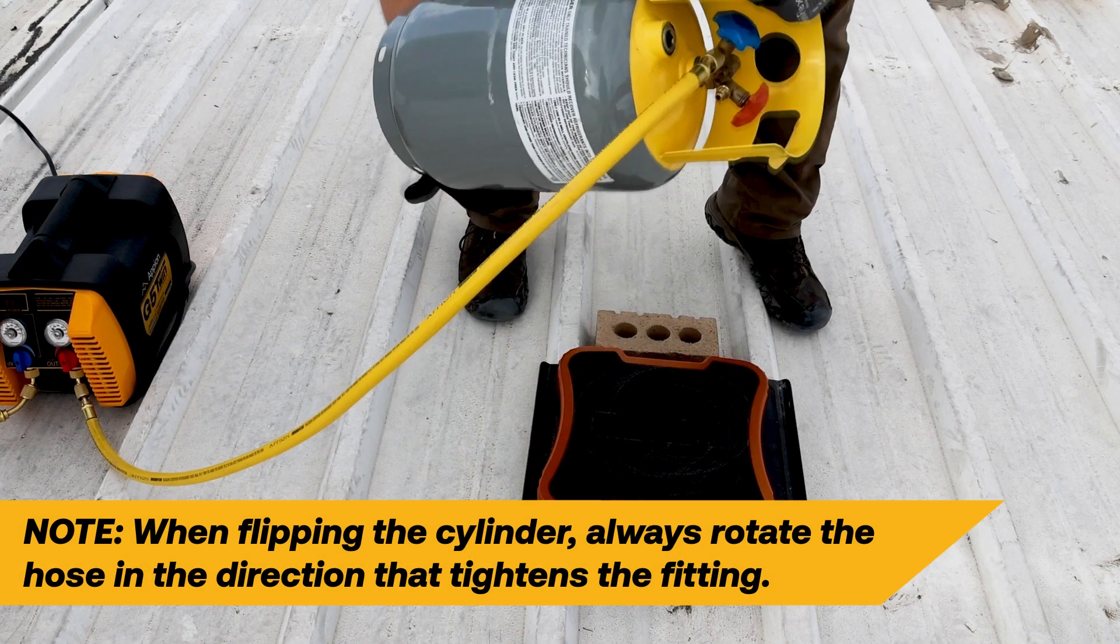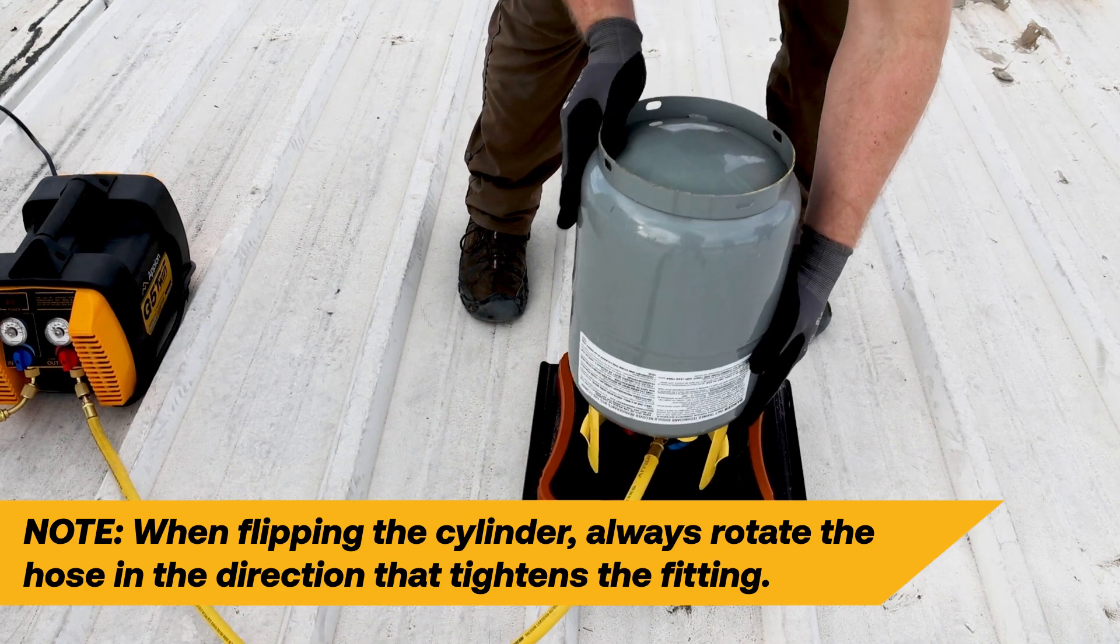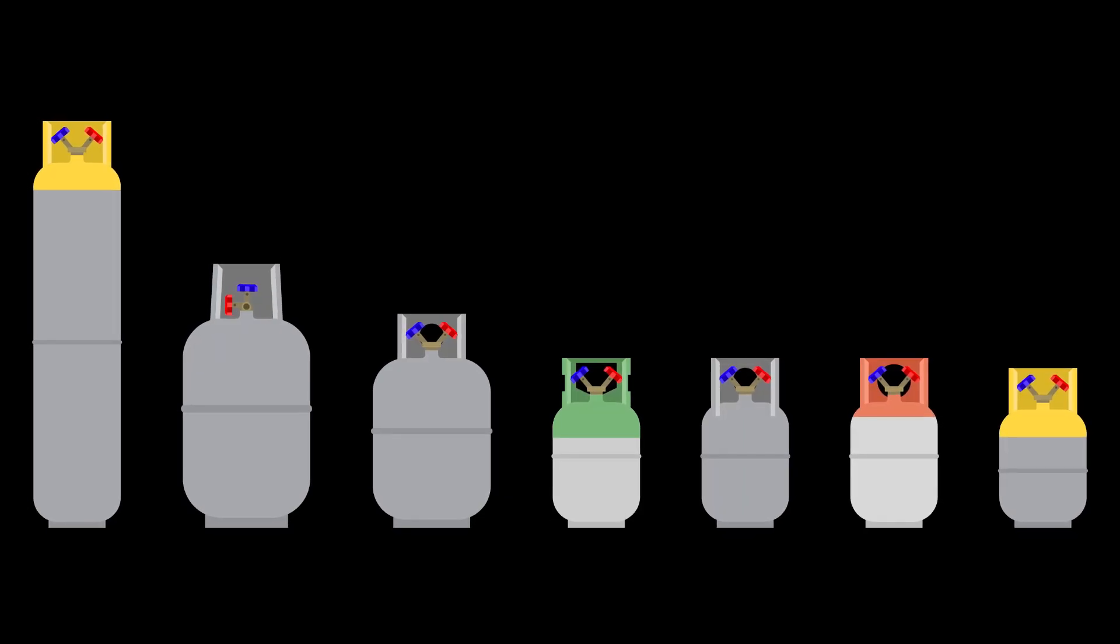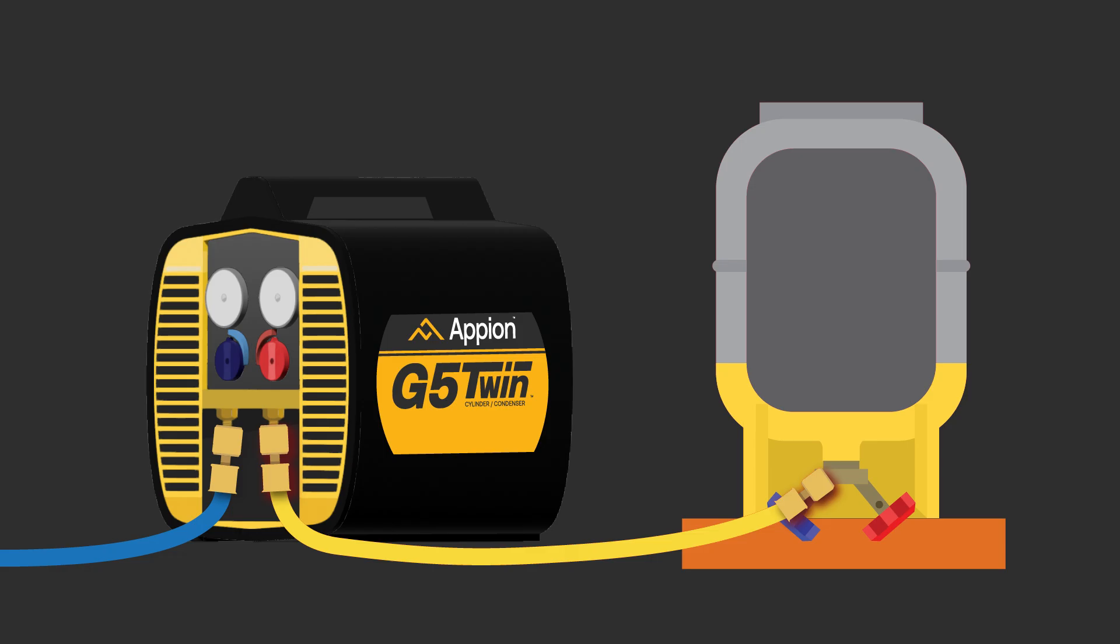One of the easiest add-on techniques is flipping the recovery cylinder. While this technique can only sometimes be used due to limitations with recovery cylinder design and weight, it is often a great technique to utilize when applicable. Flipping the cylinder allows liquid refrigerant to fill from the bottom up but through the less restrictive vapor port.